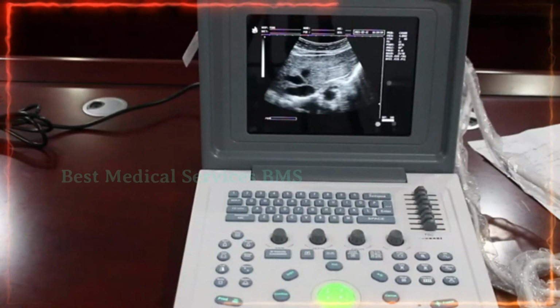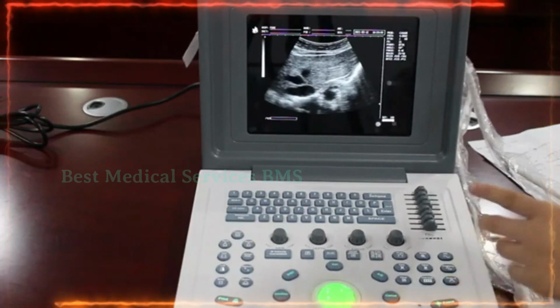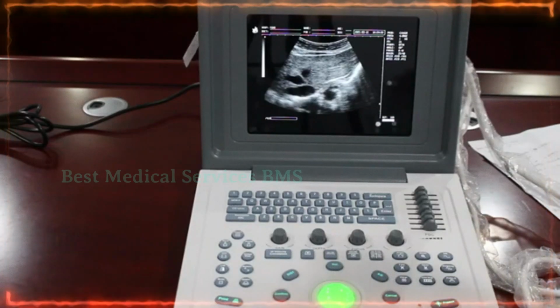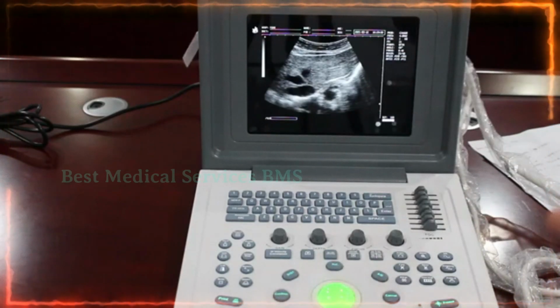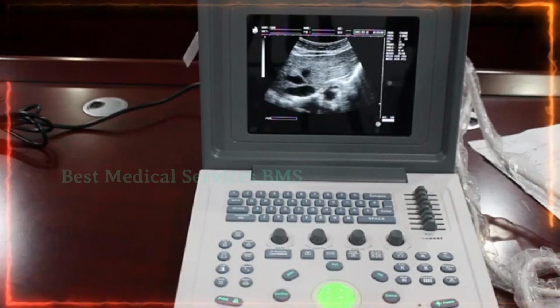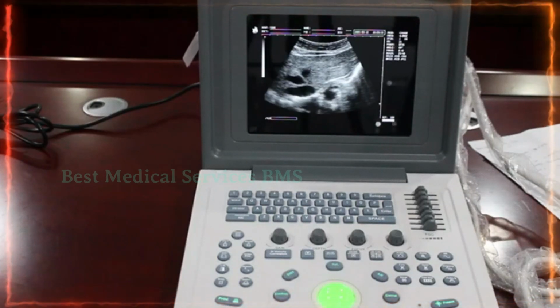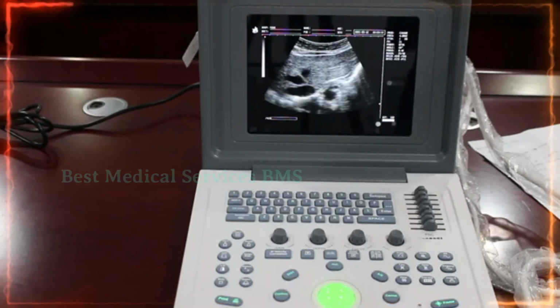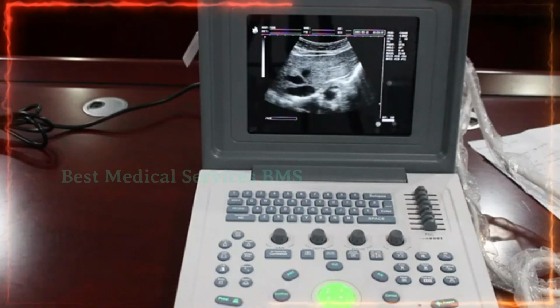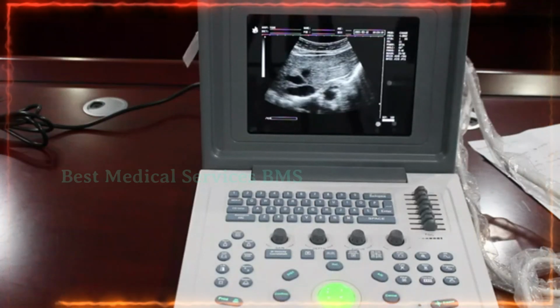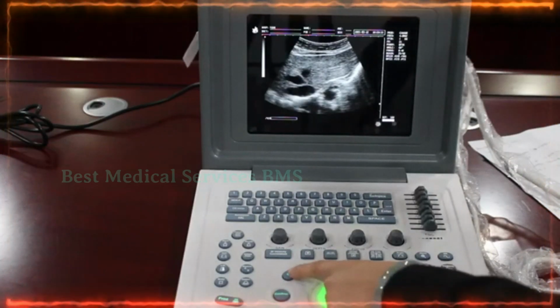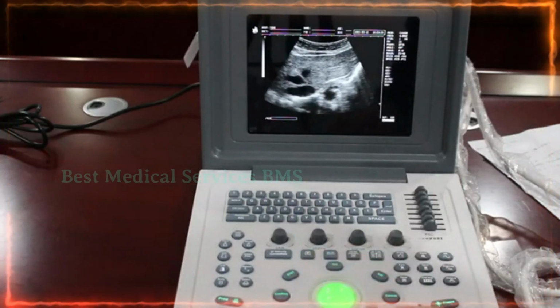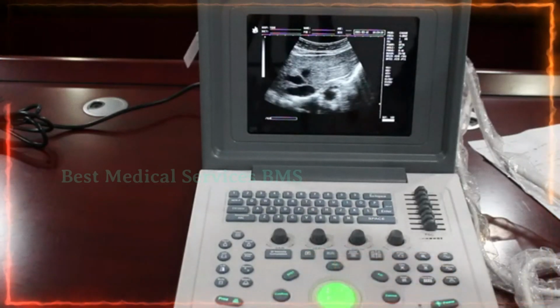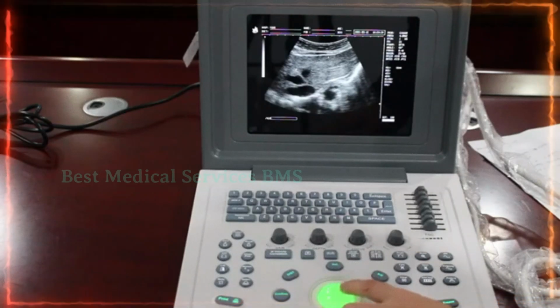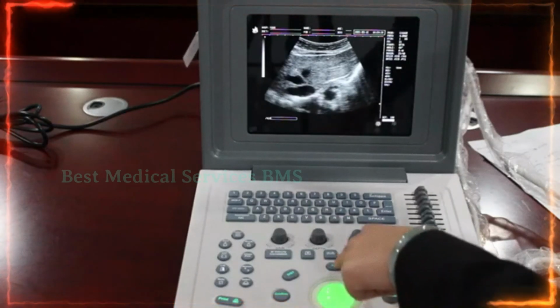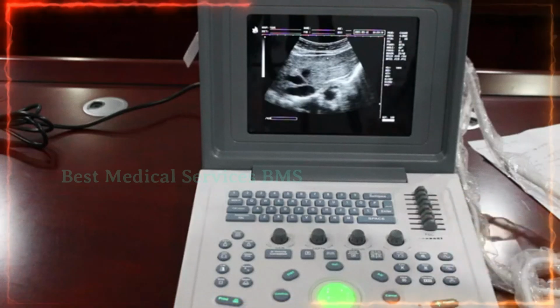When we get the ideal image, we press freeze to save the image, and then we do the measurement. We have distance measurement, area and perimeter measurement, volume measurement, cardiac measurement and obstetric measurement. So for distance, let's try pressing distance and press V4 to start the measurement, move the trackball, and press V4 again to add the measurement.